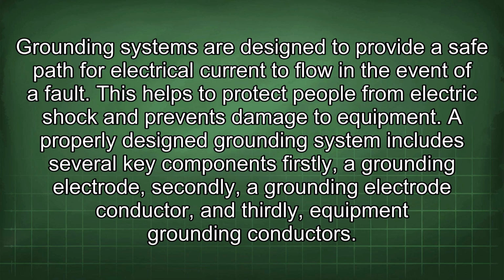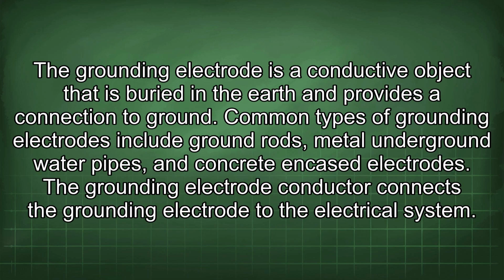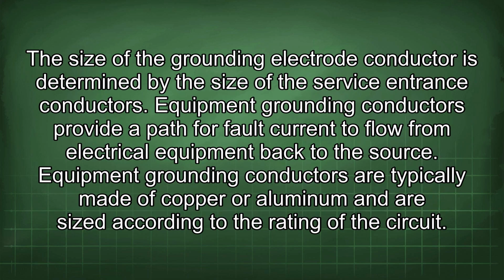Firstly, a grounding electrode. Secondly, a grounding electrode conductor. And thirdly, equipment grounding conductors. The grounding electrode is a conductive object that is buried in the earth and provides a connection to ground. Common types of grounding electrodes include ground rods, metal underground water pipes, and concrete encased electrodes. The grounding electrode conductor connects the grounding electrode to the electrical system. The size of the grounding electrode conductor is determined by the size of the service entrance conductors.